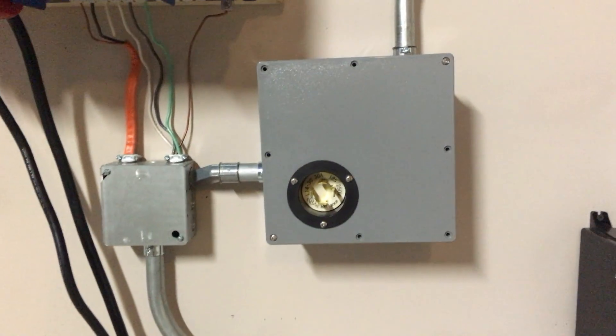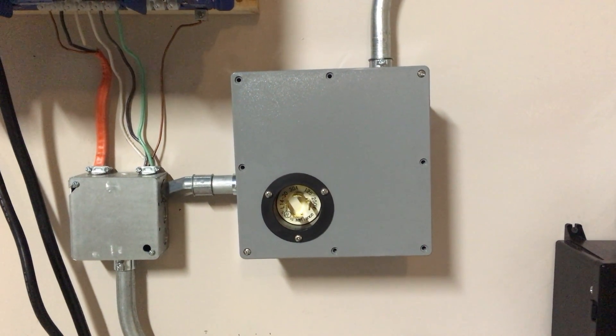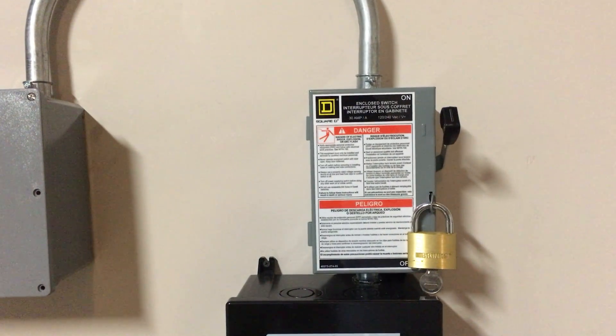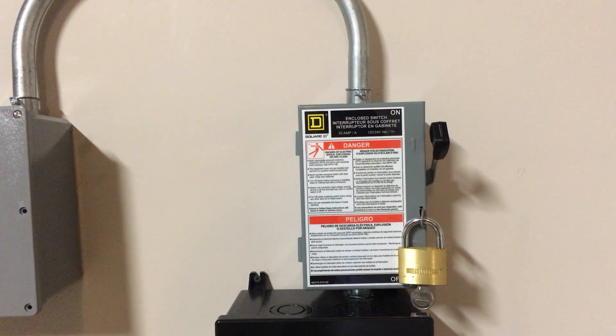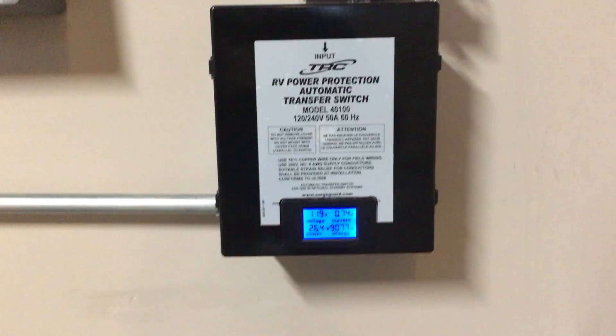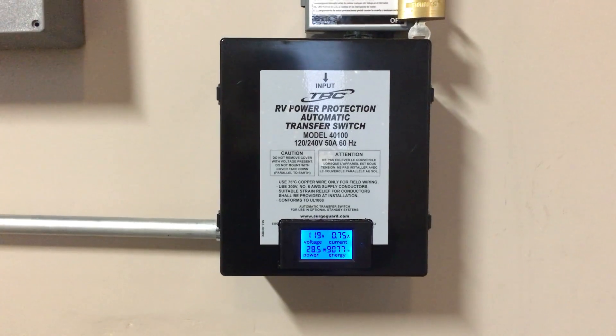This junction box has utility power coming in as well as generator power coming in, that feeds into a main disconnect switch. This will disconnect the generator as well as utility power in the event there's some kind of issue where I need to shut them both down. This right here is an automatic transfer switch.